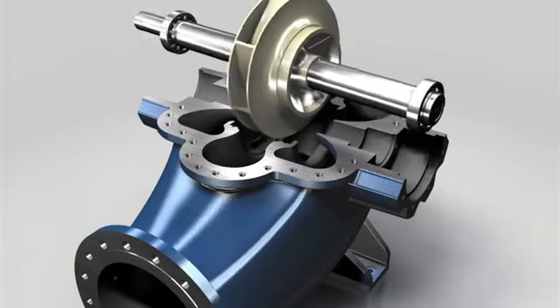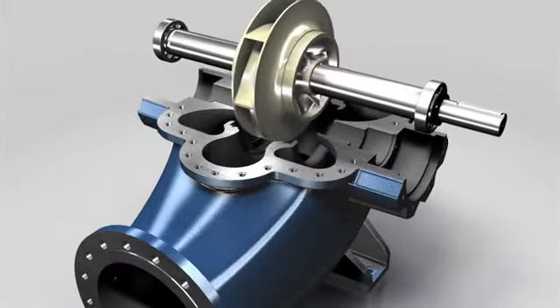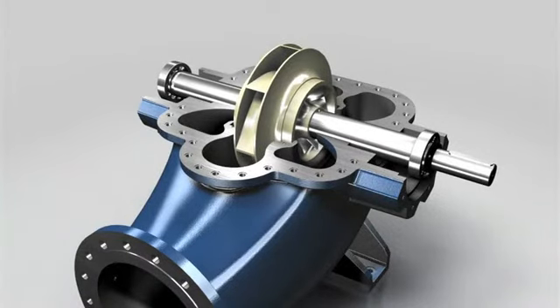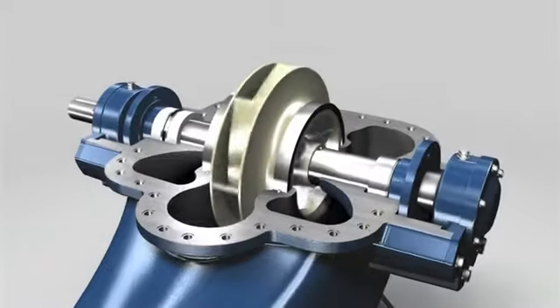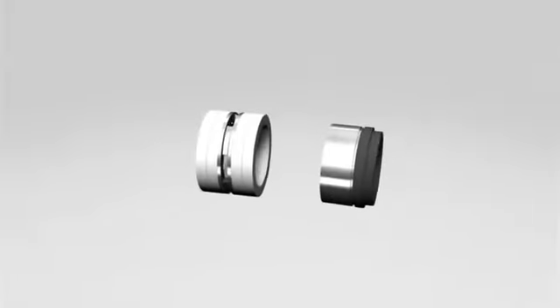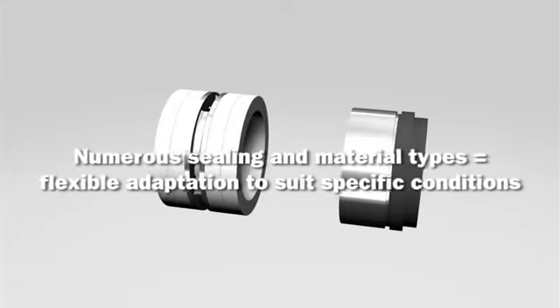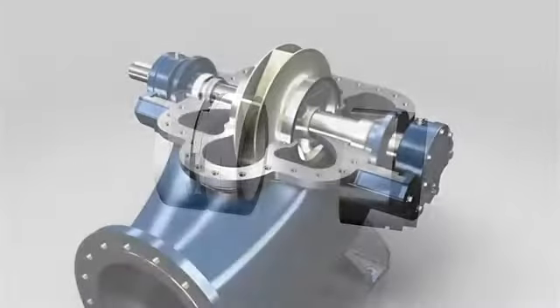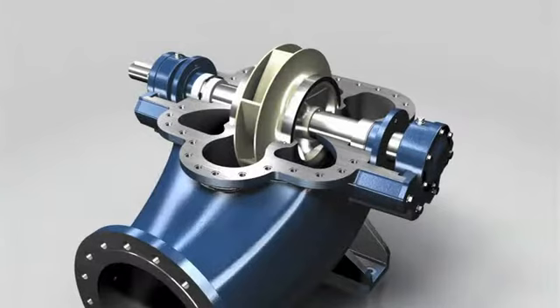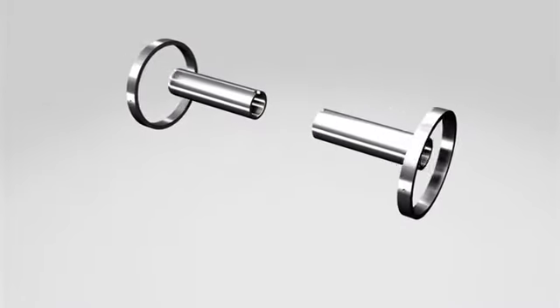The symmetrical design and identical components allow the drive to be positioned on both sides. Modifications can be made with no additional parts or changes to the product required. When it comes to sealing types, Andritz offers both a proven gland packing and a maintenance-free mechanical seal featuring high-quality design. Identical seal casings make it quicker and easier to switch to a different type of seal.